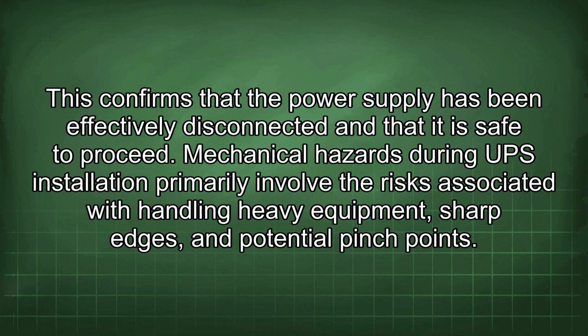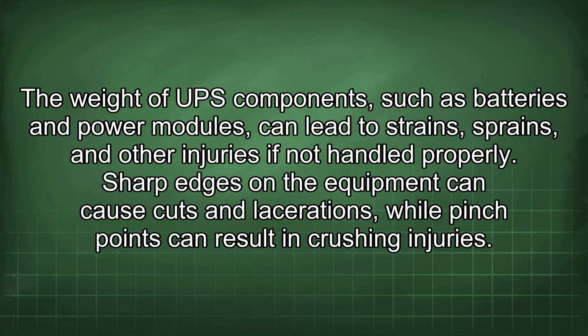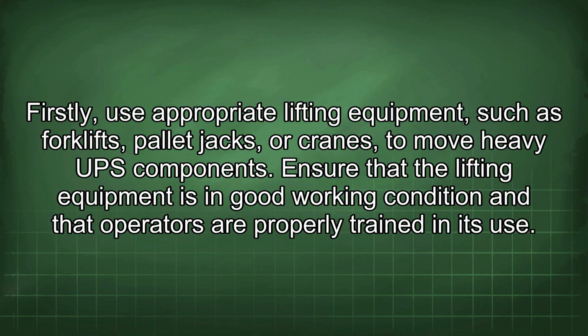Mechanical hazards during UPS installation primarily involve the risks associated with handling heavy equipment, sharp edges, and potential pinch points. The weight of UPS components, such as batteries and power modules, can lead to strains, sprains, and other injuries if not handled properly. Sharp edges on the equipment can cause cuts and lacerations, while pinch points can result in crushing injuries. Firstly, use appropriate lifting equipment, such as forklifts, pallet jacks, or cranes, to move heavy UPS components.